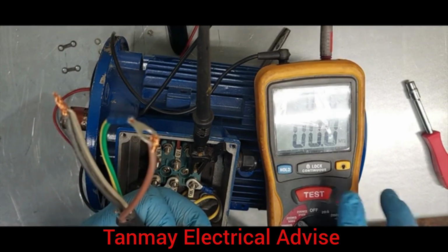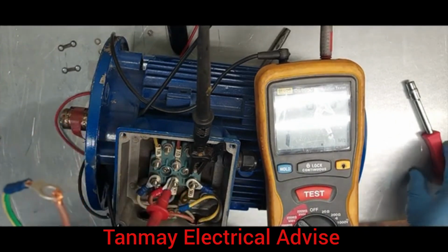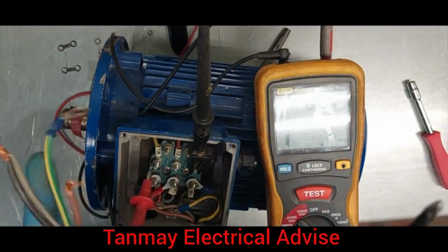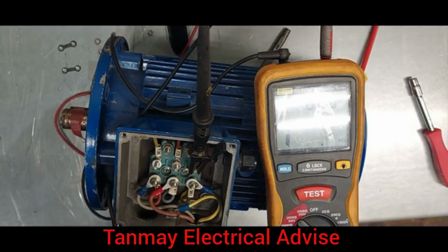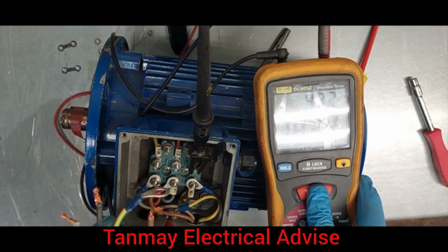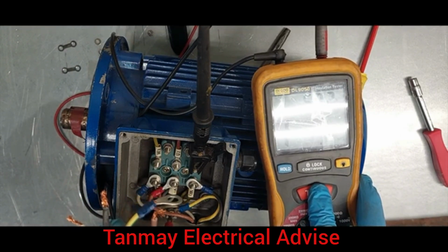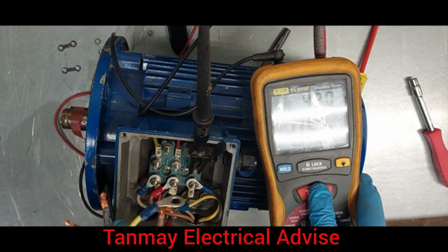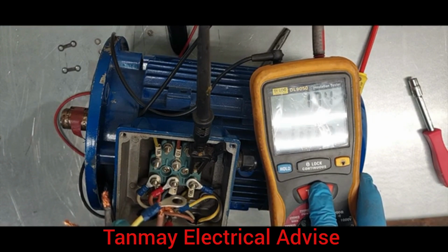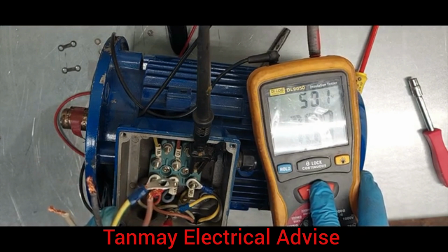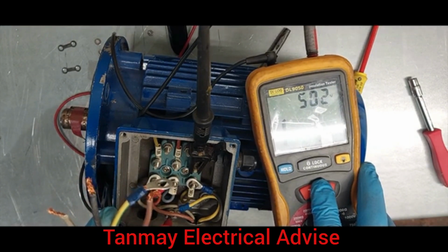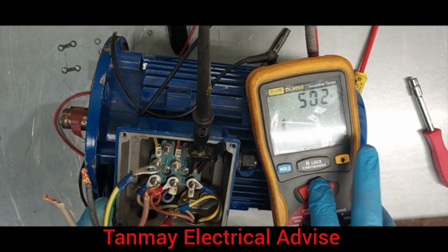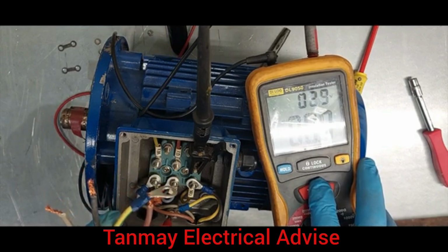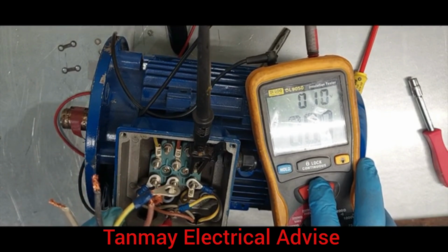So there's no insulation. What if we decide to separate them, but keep them a little bit closer? Separate them, not touching each other, but keep them close. And when we inject 500 volts, the closer it gets, the lower the insulation. So when it's separated, it's 1 mega ohm, but when it's close by, the resistance drops.